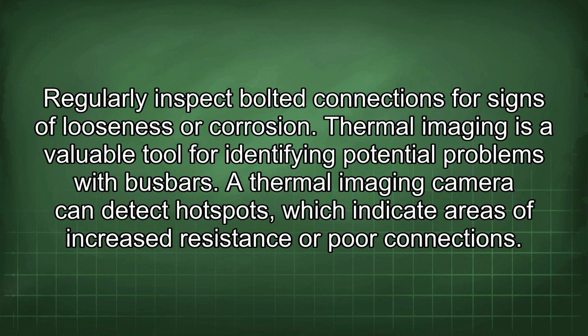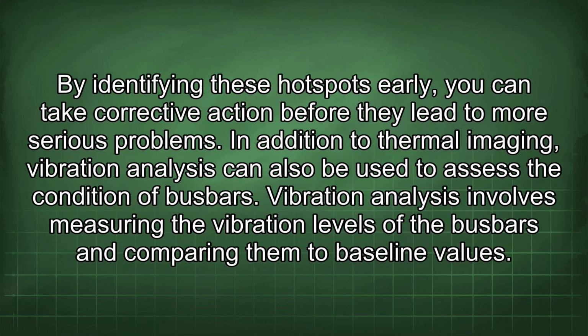Thermal imaging is a valuable tool for identifying potential problems with busbars. A thermal imaging camera can detect hotspots, which indicate areas of increased resistance or poor connections. By identifying these hotspots early, you can take corrective action before they lead to more serious problems.